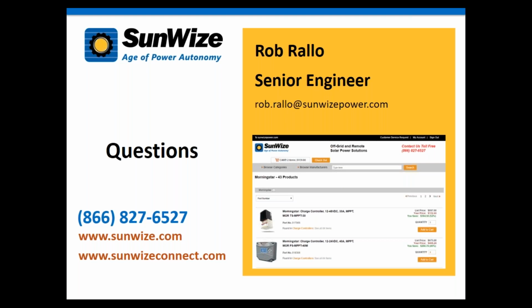Now, we'll say this: this gets back to what I was saying before with regards to fan and active cooling or active ventilation. If your NEMA 3R is not adequate, and you are actually getting a buildup of heat in there, then yes, active cooling or just a fan would be helpful, because you could also be getting a buildup of gas in there as well. So if that's the case, then yes, but hopefully you've got enough of a passive flow of air going through that 3R enclosure that that's not necessary.